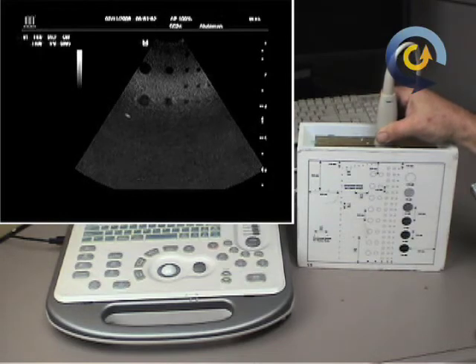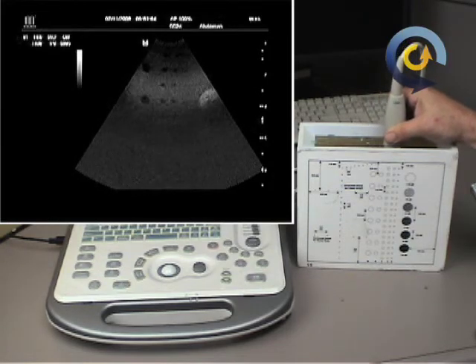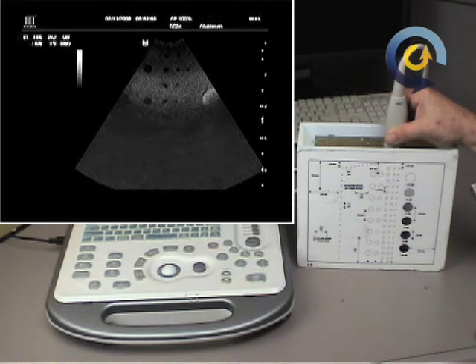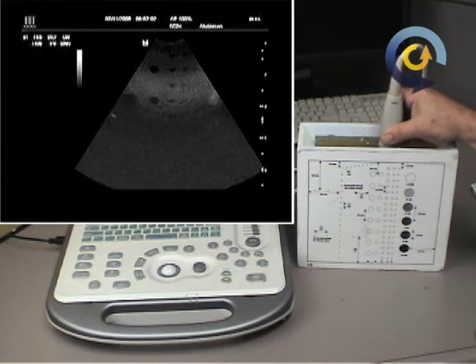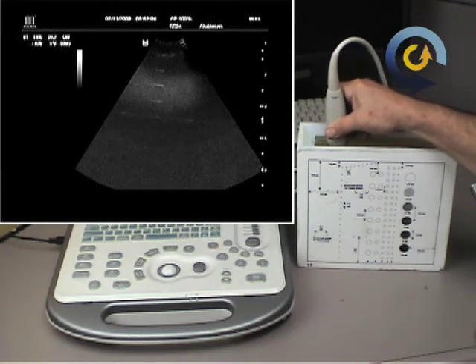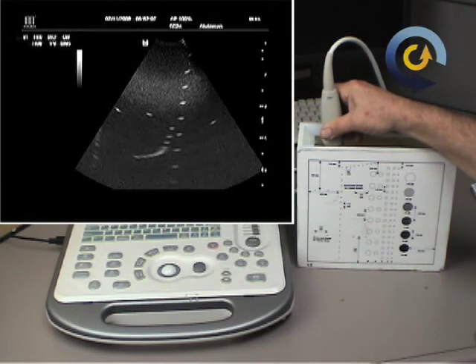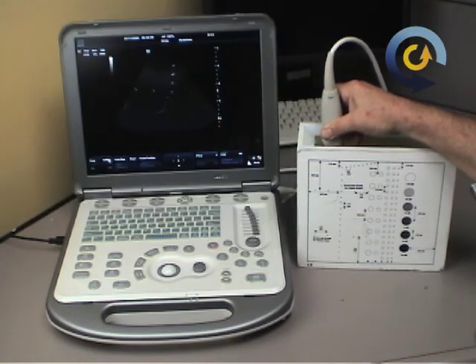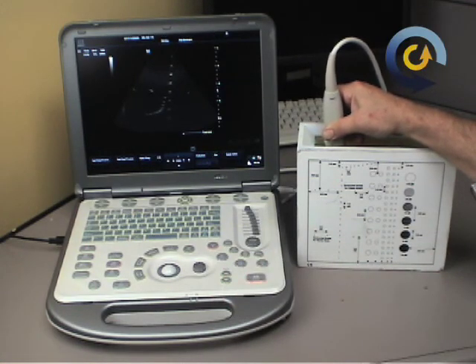So that's a use you're going to find of your transducer. It's much easier than scanning your body. Your body's a great phantom if you do yourself all of the time and you're very familiar with it, but this has the advantage of being able to document the exact same settings, exact same everything on each system you're looking at, and to be able to track it through time. Use your phantom well, it'll help you out, and it will very easily show you if you've got issues with the system or not. And that's it for a 2-minute tip today.